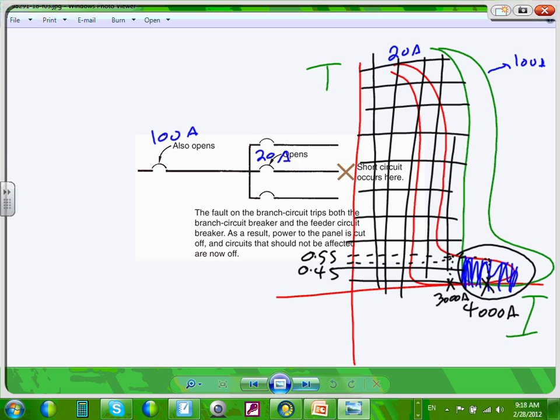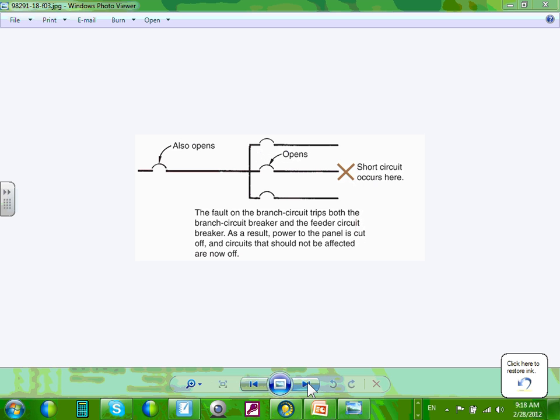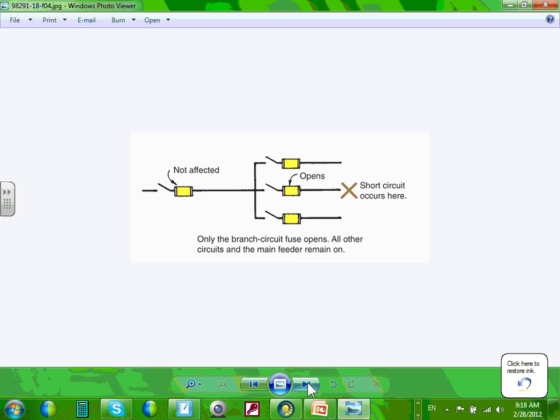I'm going to leave it at this because you guys are going to do overcurrent coordination with Chad next quarter. So you're going to learn about this. The more you learn now, the easier it will be when we move into overcurrent coordination. What coordination means is that the overcurrent device closer to the fault will open, guys. Here's a fully coordinated system. Look at this fully coordinated system here.